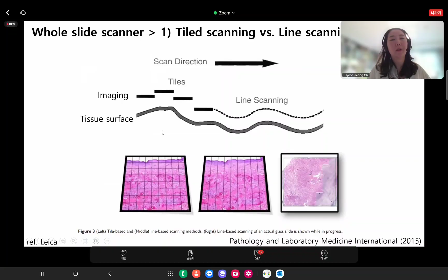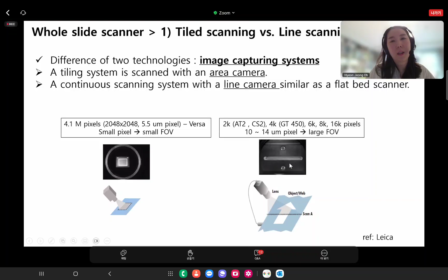Let's look at the principal methods of scanning. There are two principal methods: tile scanning and line scanning. You can see tile scanning on the left side, and line scanning on the right side. The major difference between the two technologies is the image capturing camera. The tile system scans with an area camera, whereas line scanning uses a line camera, similar to a flatbed scanner. Tile scanning captures the image in small sections and then stitches them together. On the other hand, line scanning captures the image continuously line by line, which can result in faster acquisition and fewer stitching errors.